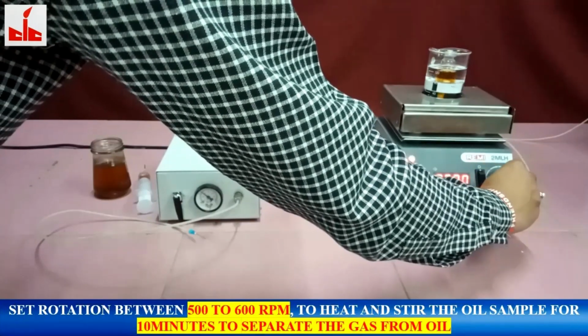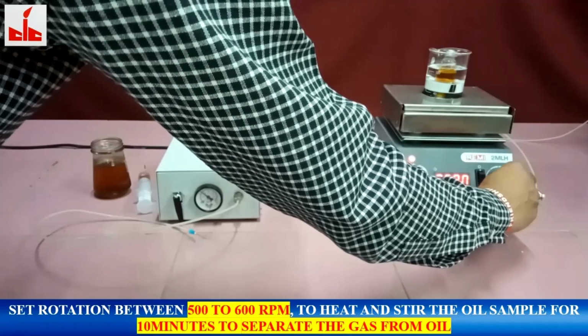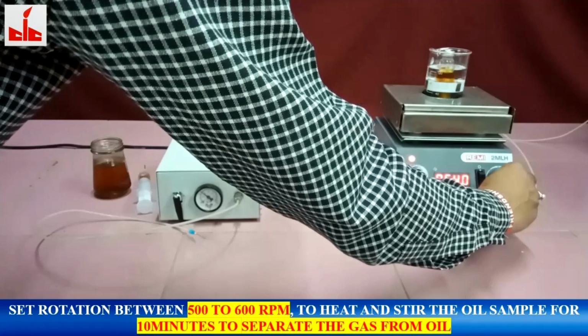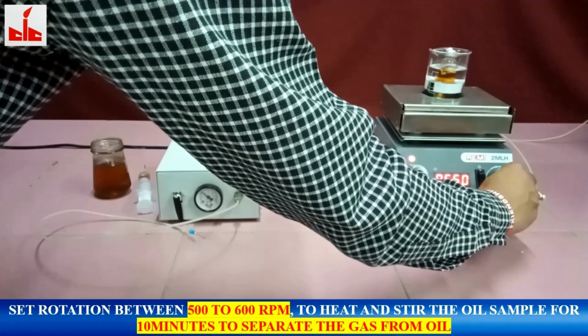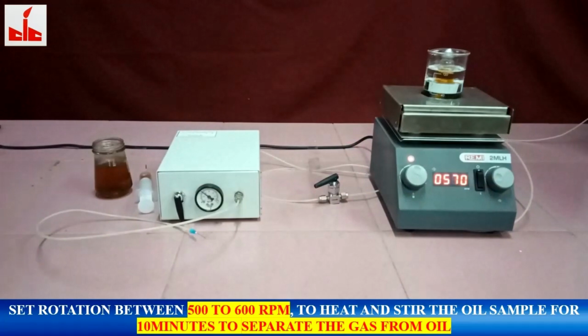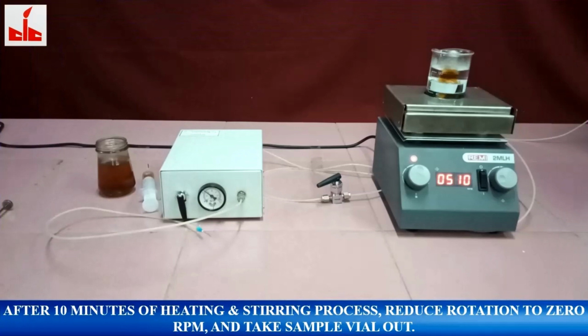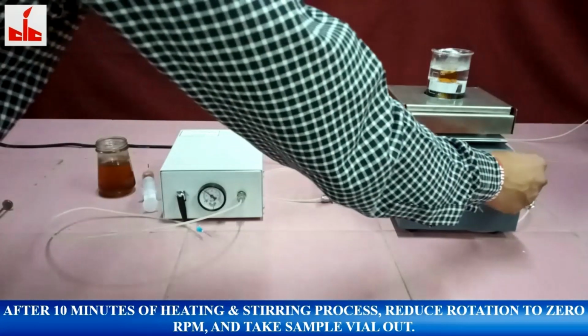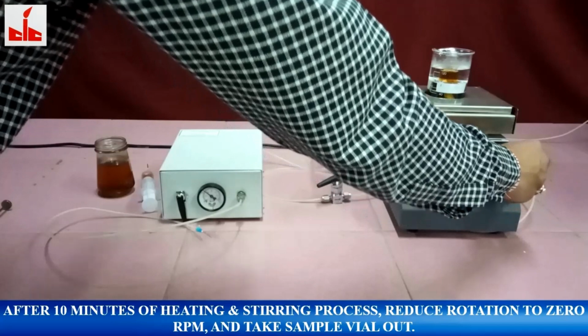Set rotation between 500 to 600 rpm to heat and stir the oil sample for 10 minutes to separate the gas from the oil. After 10 minutes of heating and stirring, reduce rotation to 0 rpm and take the sample vial out.